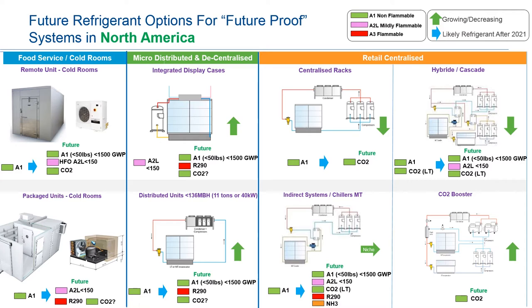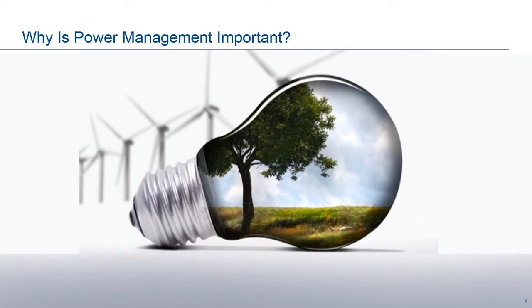134A with CO2 subcritical low temp is very efficient. Indirect chillers offer a lot of choice on the refrigerant depending on where the chiller is installed. If the equipment is out on the roof, there are systems using propane or ammonia, chilling a CO2 loop and pumping CO2 as a secondary fluid to medium temp, and using that condensing for low-temp Cascade CO2 as well. There are all kinds of refrigeration architectures, and all of them have an energy component — that's why we use life cycle climate performance analysis to compare different architectures.